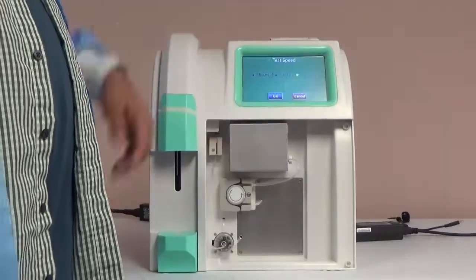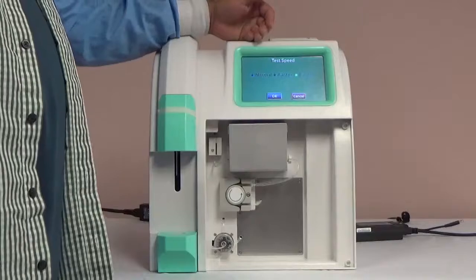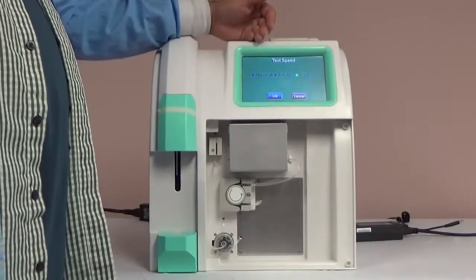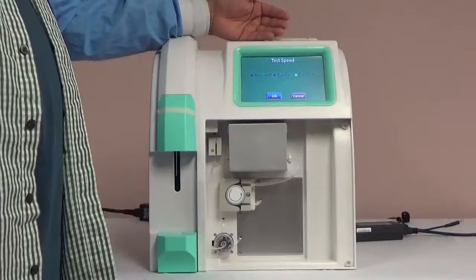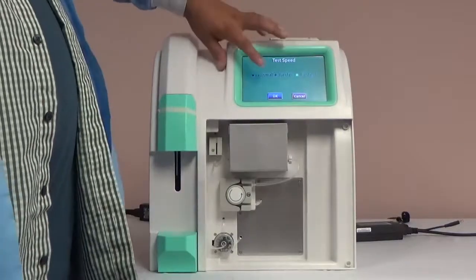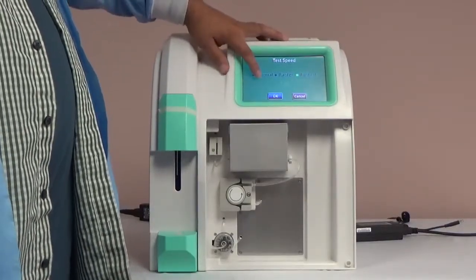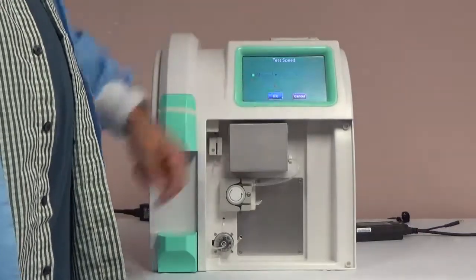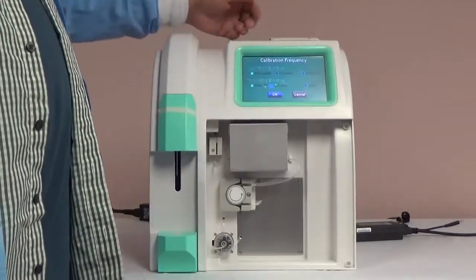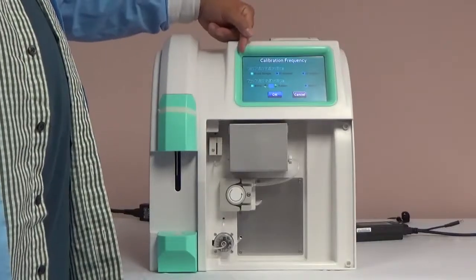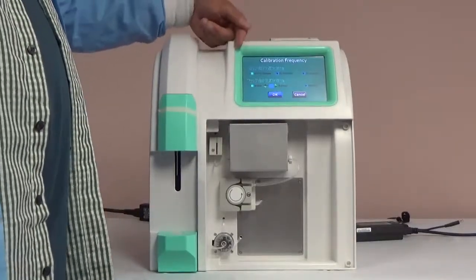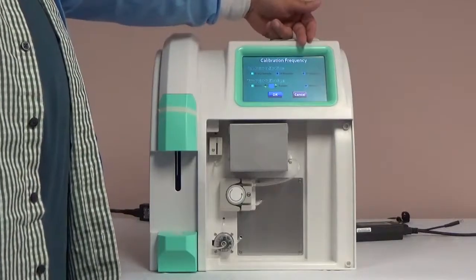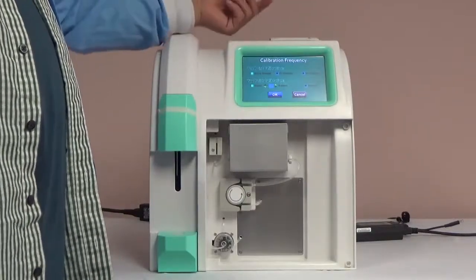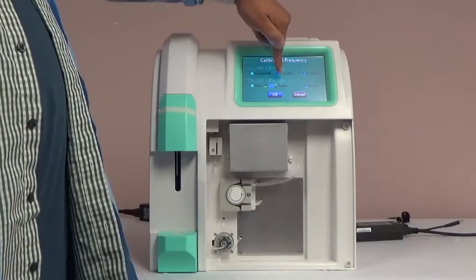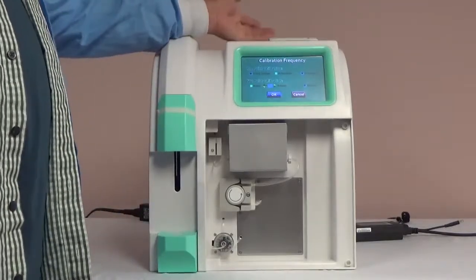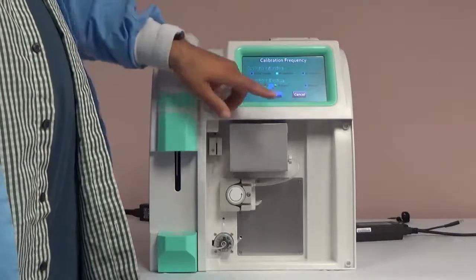The test speed setting is how fast the analyzer calculates the result. This doesn't affect the amount of reagent used, but the speed it takes to calculate results. For best results in reproducibility, we recommend it is set at normal. On the calibration frequency screen, you can adjust the 1-point and 2-point calibration. These calibrations are performed during the sample testing. The recommended settings for these calibrations is every 10 samples for a 1-point calibration and every 20 samples for a 2-point calibration. If you adjust these settings, save your settings by selecting OK and return to the main menu.